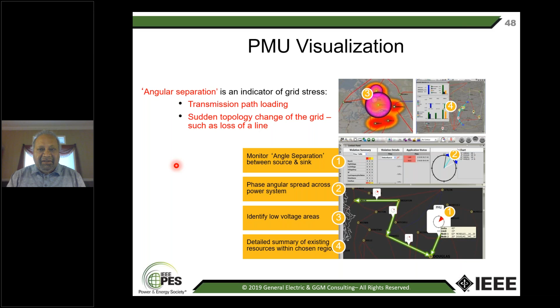So this is an example of if we had PMUs on August 14th, 2003. If we had a PMU at Cleveland and one in West Michigan, and you monitored the angle difference between the two, you would have noticed that the angle difference kept increasing over time. And eventually it led to collapse. So the thing was, we had an hour to react, analyze, and mitigate this issue. So all it would have taken is for a Cleveland person to call West Michigan and say, hey, what's happening? We're drifting apart.